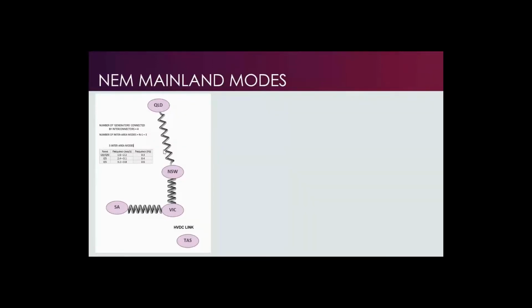The theory says that if there are n generators, there will be n minus 1 inter-area modes, 3 in this case, since there are four generators connected by interconnectors. So n minus 1 is 3, meaning we will have 3 inter-area modes on the mainland NEM. The mainland is connected to Tasmania via an HVDC link, and electromechanical modes will not propagate to Tasmania and back. Tasmania has its own electromechanical modes.